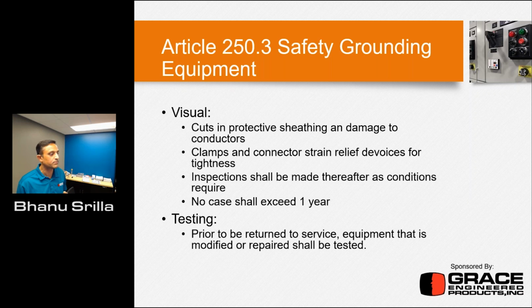And testing has to be done prior to the return to service of equipment that is modified or repaired. So whenever, as I mentioned before, you perform any kind of maintenance or repairs, you need to make sure that equipment is tested in accordance with the manufacturer guidelines or the industry standards before you put it back in service condition.